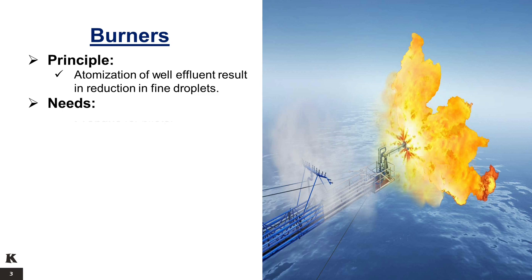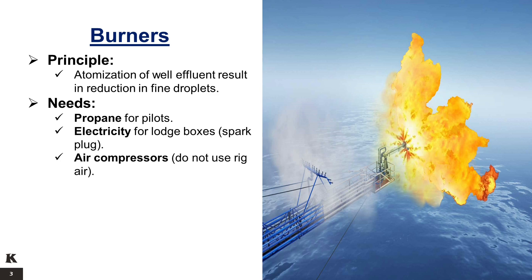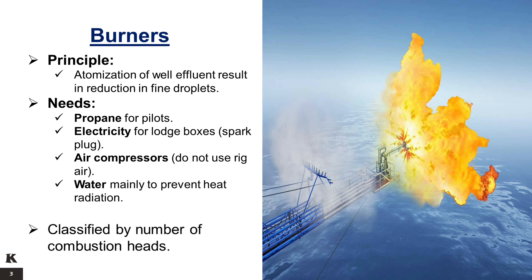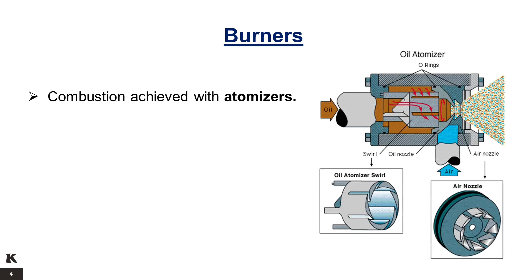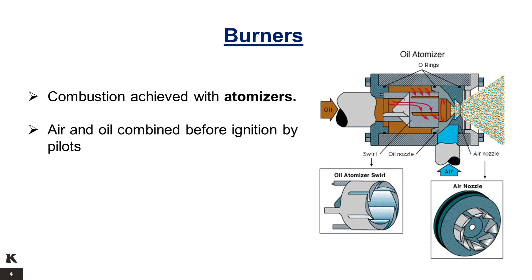The burner needs propane for pilots' light, electricity for lodge boxes or spark plug, dedicated air compressors — do not use rig air — and water, which is mainly required to prevent heat radiation. The burners are classified by number of combustion heads, which determines the maximum oil flow rate. Oil combustion is achieved with oil atomizers, where the air and the oil are combined in the atomizer before ignition by the pilots.